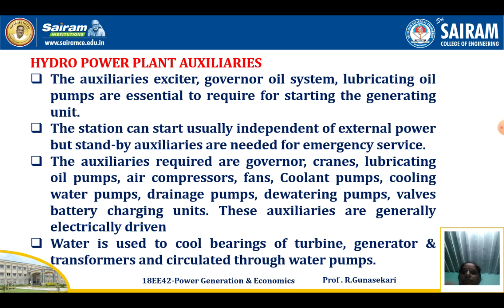Then, hydropower plant auxiliaries. The auxiliaries, that is the exciter, governor oil system, and lubricating oil pumps, are essential and required for starting the generating unit. The station can usually start independent of external power, but standby auxiliaries are needed for emergency service.